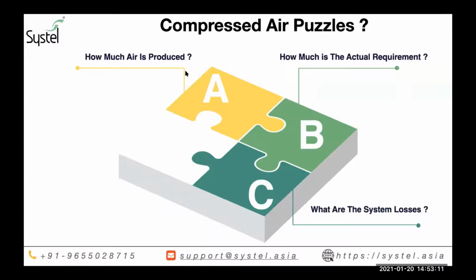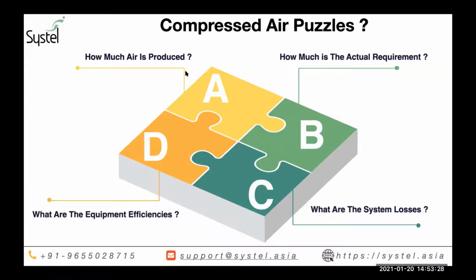Unless those are being quantified and the gaps have been identified, it will be very hard for you to maintain a system which has low leakage or low loss levels. And finally, about the equipment efficiencies, this is also highly questionable in many areas where they don't have metering for monitoring the compressor's specific power, or the dryer's pressure dew point, or the pressure drops across each treatment or filter equipment. When we don't have answers for the four questions that I raised above, it is going to result in inefficiency.